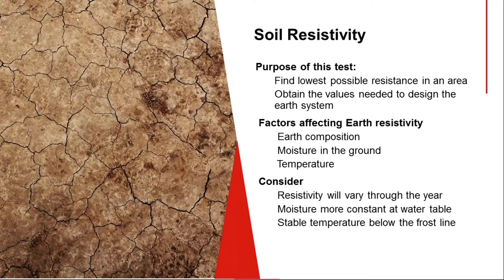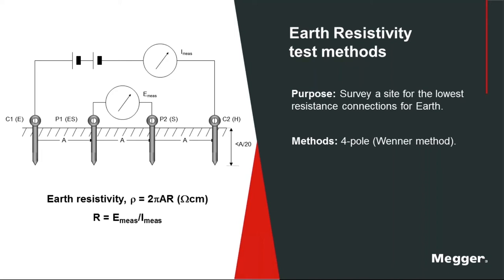You can take a standard ground tester. The one thing you have to know here is it must have four terminals. Some ground testers only have three terminals. With three terminals you can do a ground test of your electrode, but you cannot do a soil resistivity test unless you have four terminals. This is what is commonly referred to as Wenner method, named after Frank Wenner.